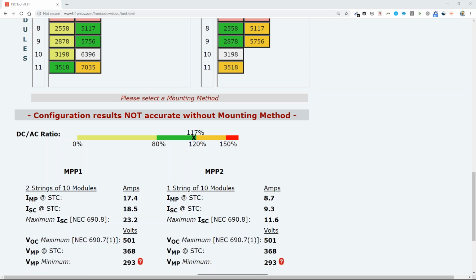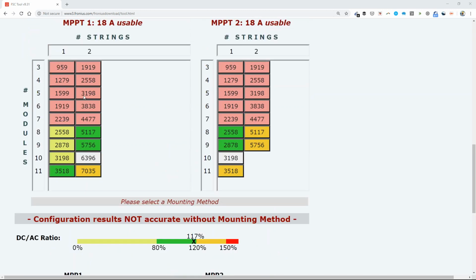within range. It's saying you're not doing excessive oversizing, you're right on the edge, but that's fine. That's optimal. Or I could do 2 strings of 8, that's 16, and then 2 strings of 7 for 14, but it's saying this 2 strings of 7 might be a little bit undersized. It could benefit from a slightly larger circuit to hit that minimum operating voltage.